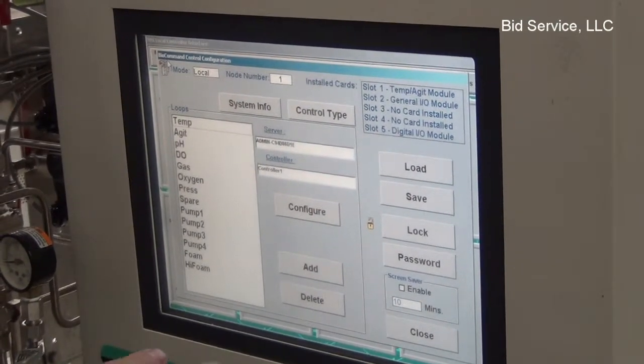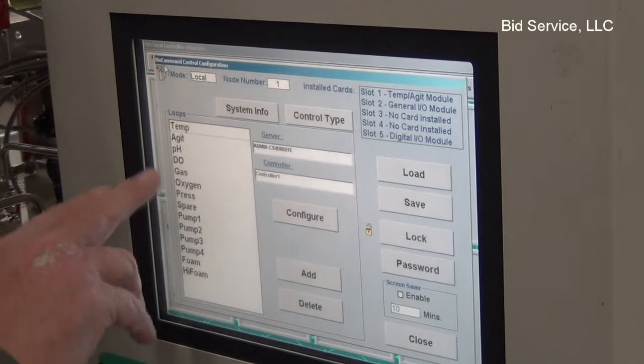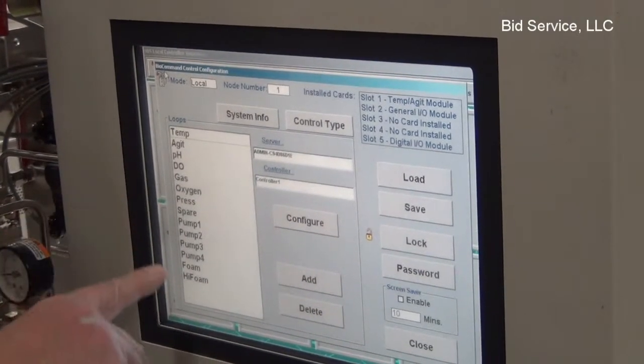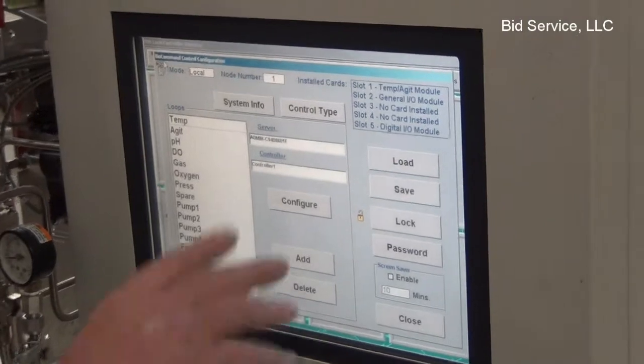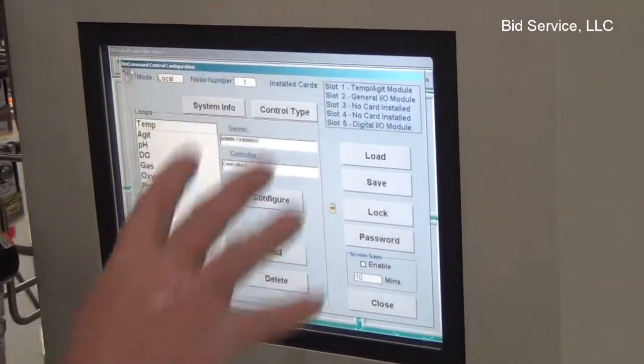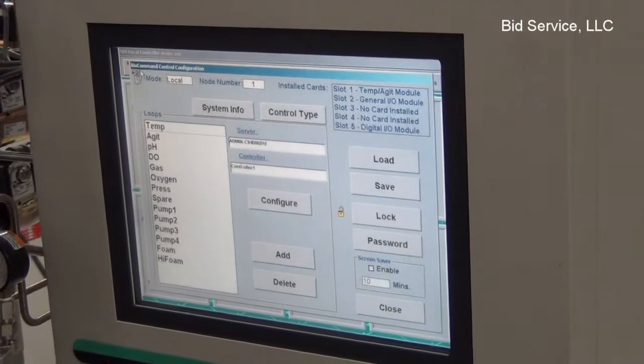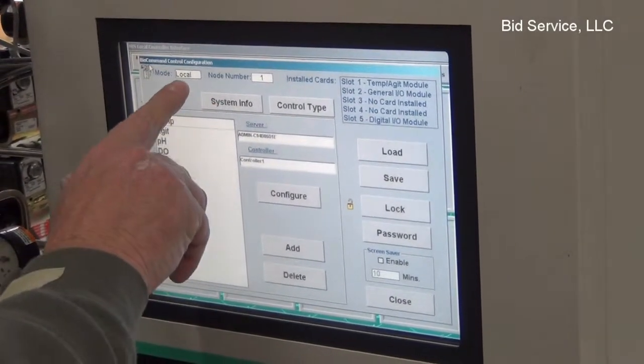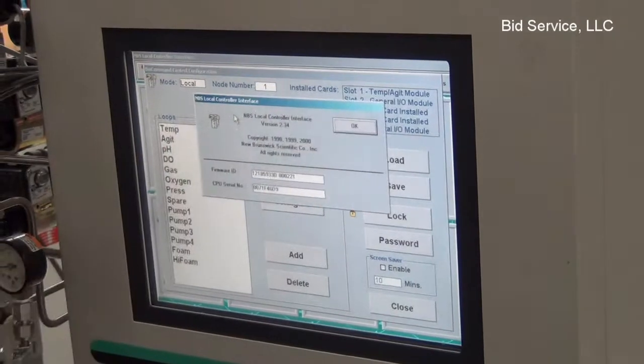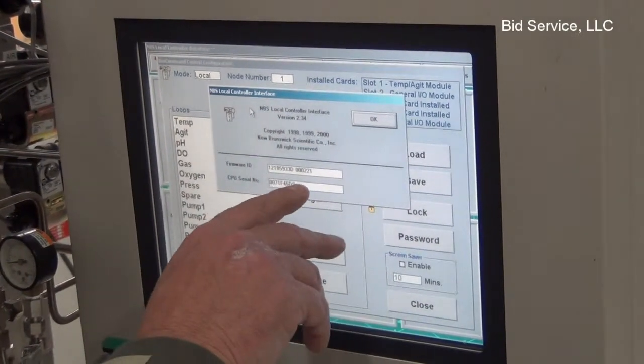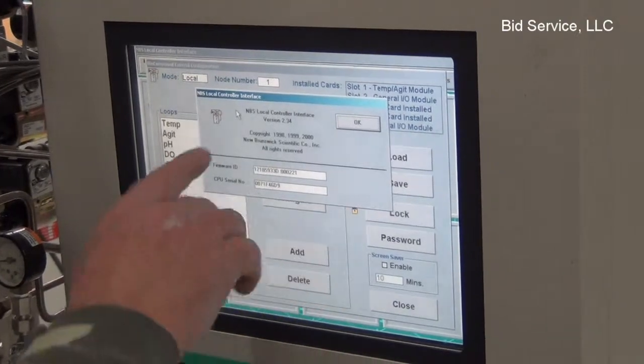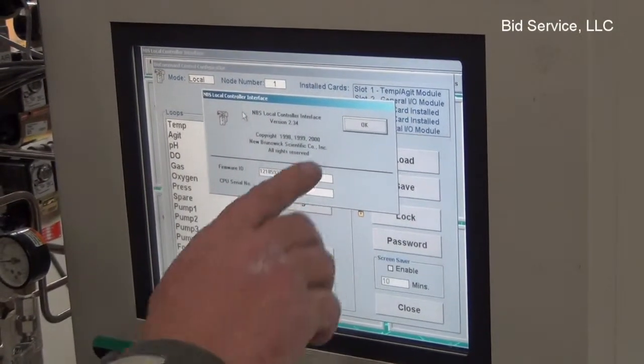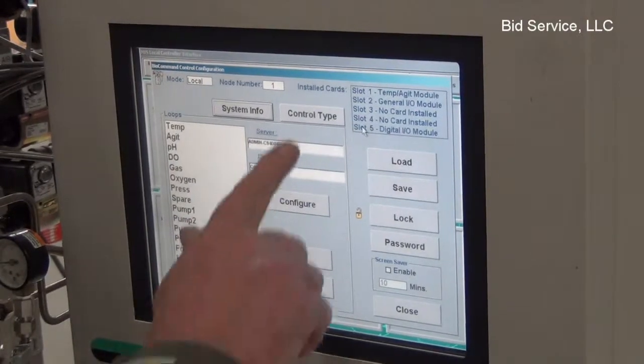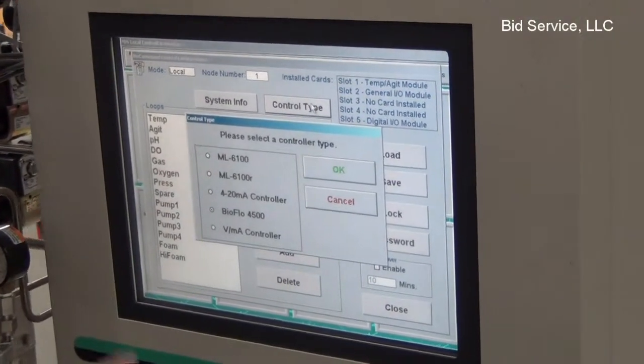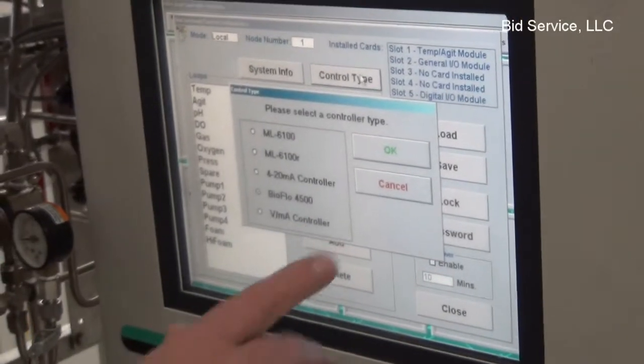If I go to configuration, it brings up this page, shows you what's installed, the loops that have been configured, which is all what you saw on the gauge screen. It shows you what server it's considered. That's for if there's a computer inside here. You're in local mode, node number 1. You can hit system info. It gives you the firmware identification and CPU serial number and the version number of the controller interface. If we go to control type, it shows you it's a Bio Flo 4500.